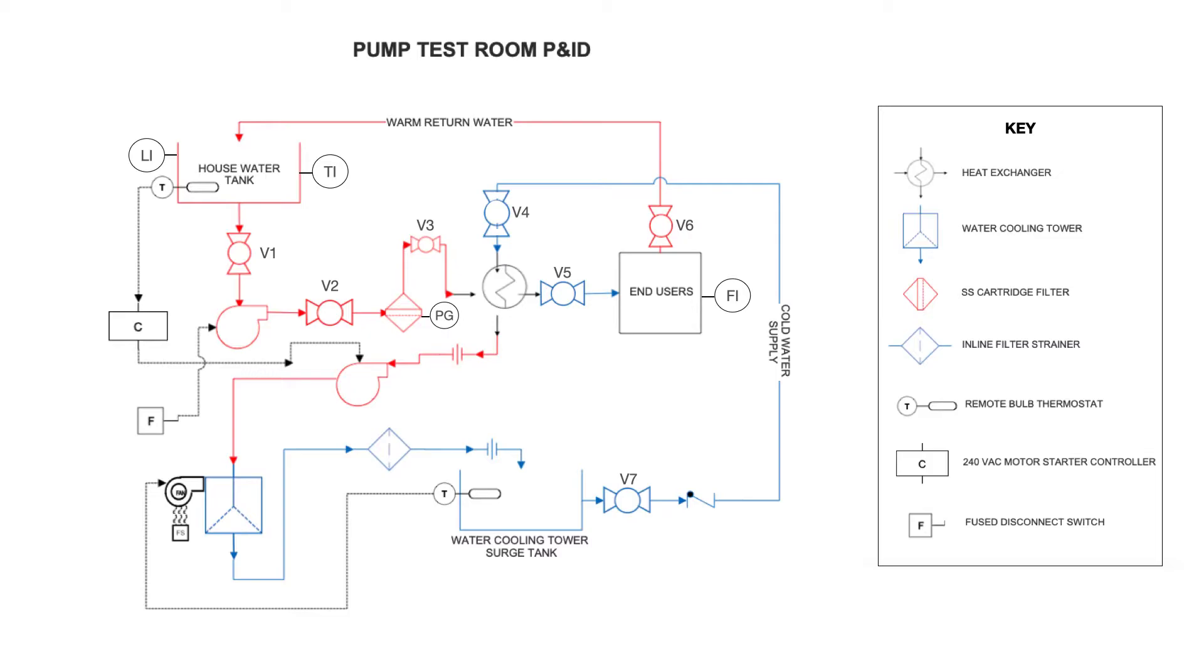And then the water is then pumped out to the water cooling tower where a fan blows a column of air up through the water which cools it down. And then as it leaves the water cooling tower, that cold water goes through an inline filter strainer. Then it goes through a union and it gets dumped into the water cooling tower surge tank and the process repeats itself over and over again.